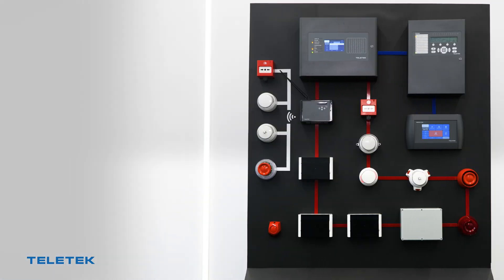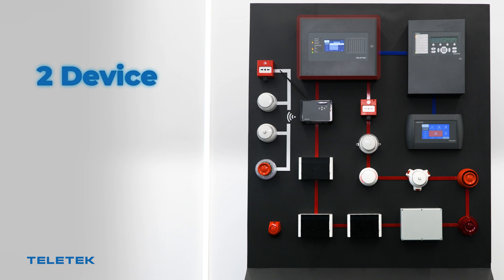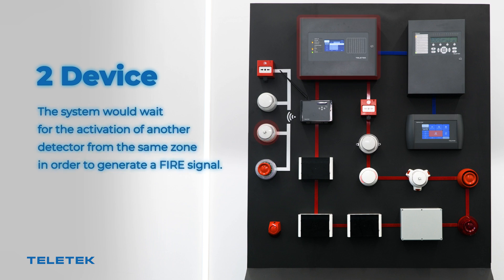Two Device mode: when this mode is selected, any detector activation within the system generates a pre-alarm event to the respective zone. But the system would also wait for activation of another detector from the same zone in order to generate a fire signal.